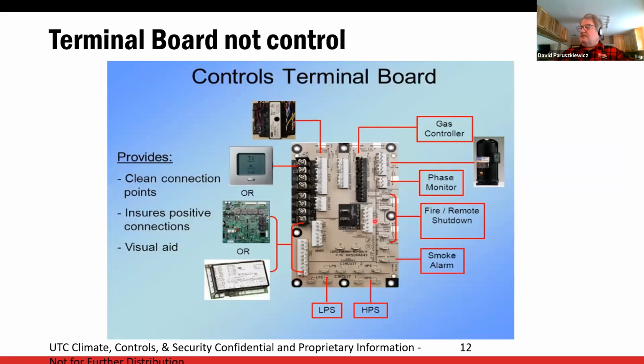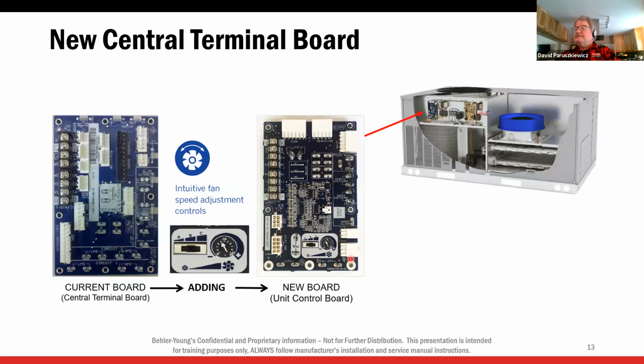Again, just to reiterate everything that it does, it's just basically a wire nut. So your thermostat connections, your economizer connections, your IGC plugs in here, your smoke detectors over here, your fire alarm, your low pressure switches. Okay, but there's really no logic on that board. There's not really much to fail on it.